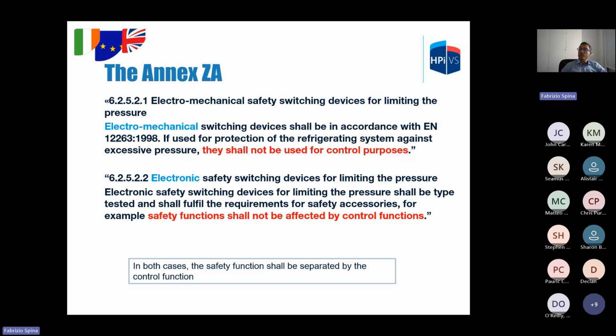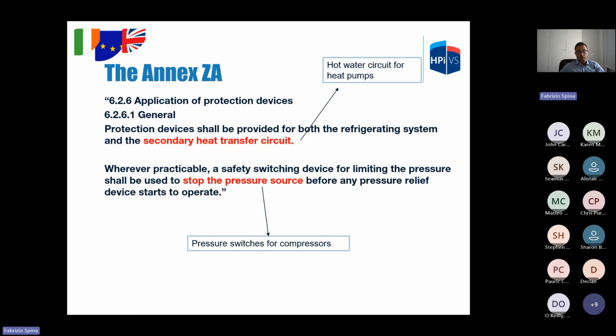Electromechanical safety switching device for limiting the pressure. The system can be provided by electromechanical or electronic safety switching. In both cases, the safety function shall be separated from the control function. So this device must be used only for safety.